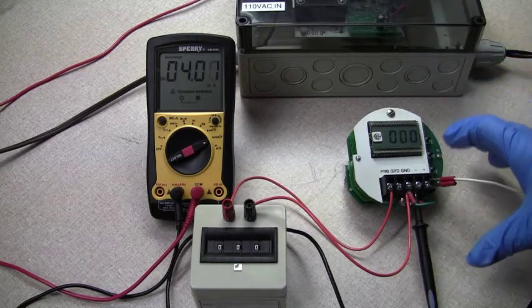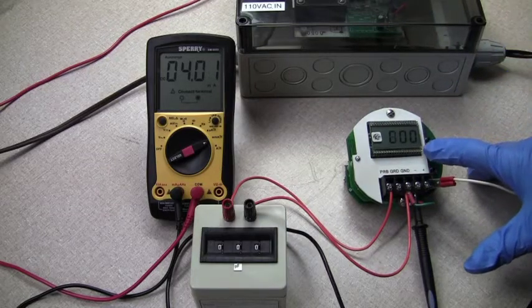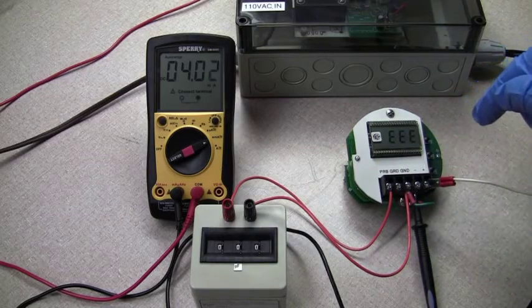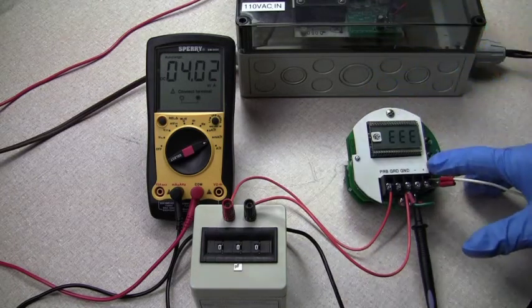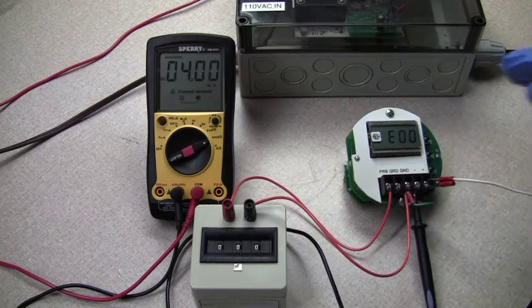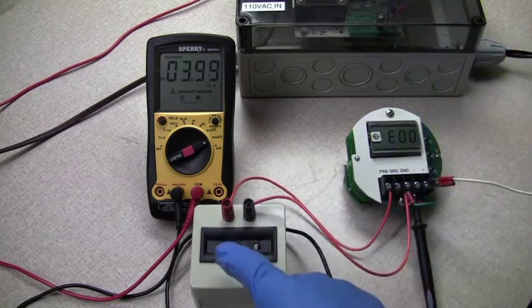Setting your low is simple. You hit the SW2 button to enter the low set point. E will display for empty. Hit the SW3 button and now you can set your low set point. So right now I have it at zero zero zero.